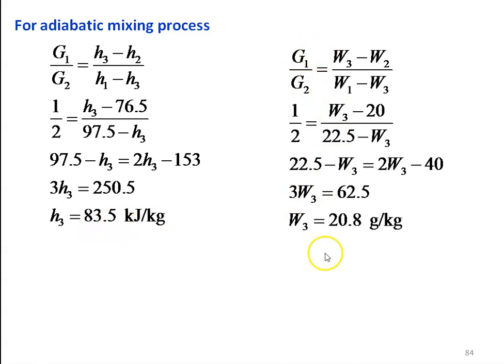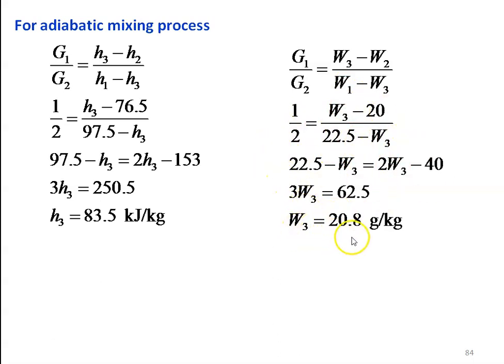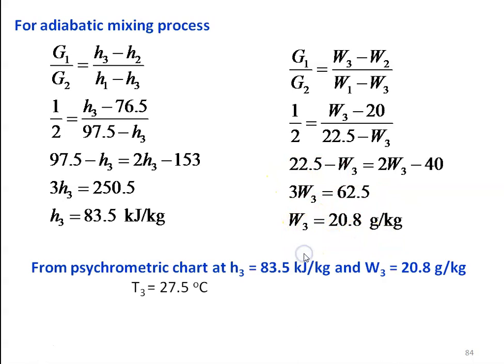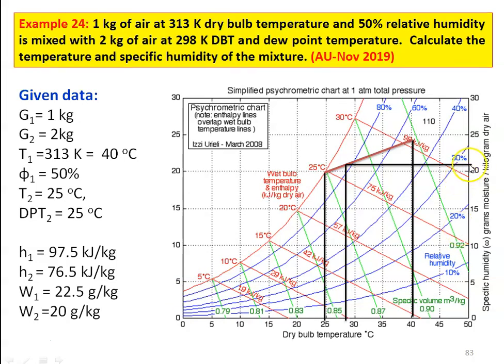Similarly, for specific humidity: G1/G2 = (W3 − W2) / (W1 − W3). Substituting: 1/2 = (W3 − 20) / (22.5 − W3). Cross-multiplying and solving, W3 = 20.8 g/kg. The corresponding temperature is 27.5°C. Locating the point for the calculated values on the psychrometric chart, the temperature is 27.5°C.